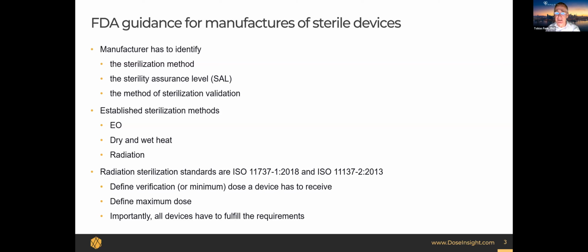And then the FDA defines established sterilization methods that are easier to go through the process than things that are not established. Established methods count ethylene oxide, which is a poisonous gas that the product is exposed to, and that takes about 50% of the sterilization market. Then there's dry and wet heat, which is rarely used in the devices we are talking about. And then the other 50% is radiation. So we are focusing here mostly on radiation sterilization.